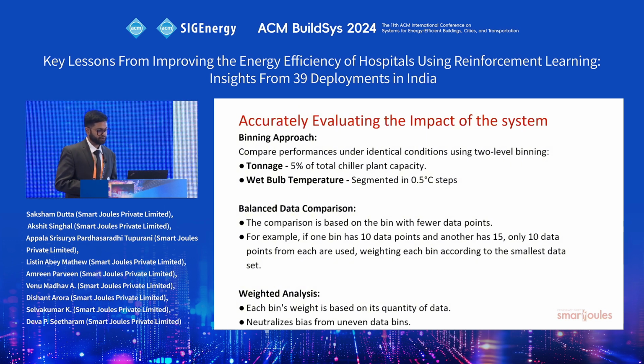We created bins based primarily on two uncontrollable parameters: wet bulb temperature representing ambient conditions and tonnage representing the building load. Tonnage was binned in increments of 5% of the total chiller capacity, while wet bulb temperature was binned in 0.5 degrees Celsius steps. These values were chosen based on how IKW per TR, which is the consumption of the high side equipment divided by the tonnage delivered, varied with changes in tonnage and wet bulb, as well as the availability of data points for comparison. In cases where there was an imbalance of data points between two time frames, we applied a weighting approach, aligning the analysis to the lower number of data points. This weighting helped us reduce any bias due to differences in data between the two time frames.